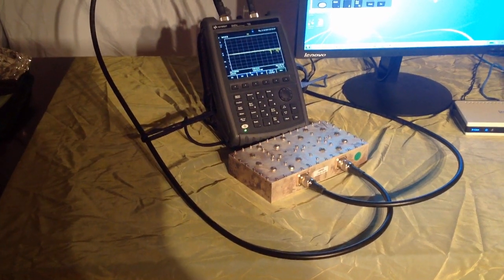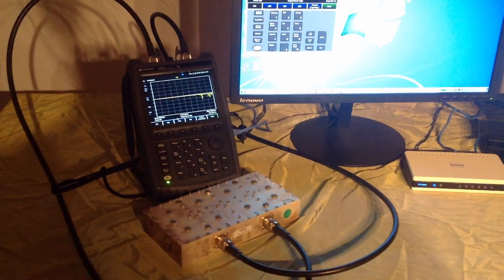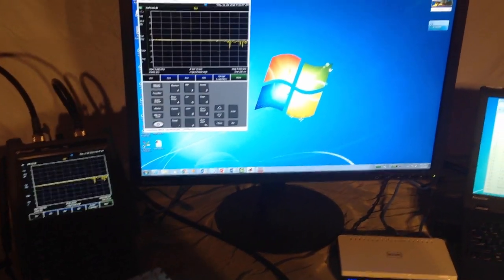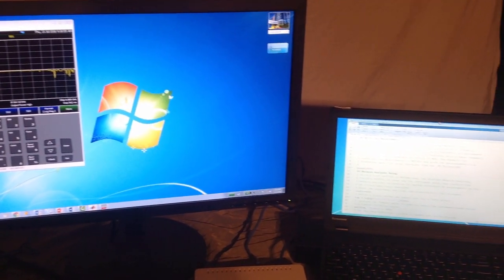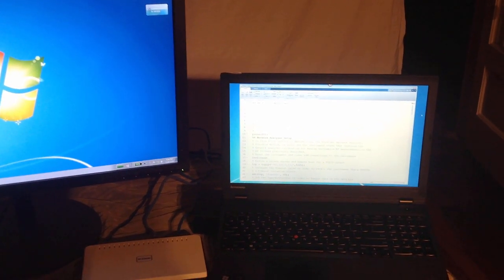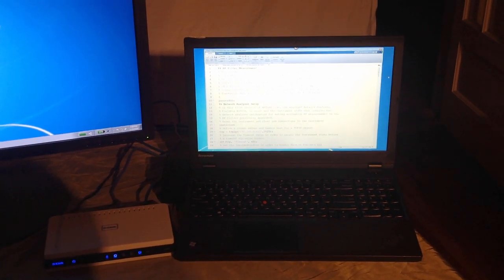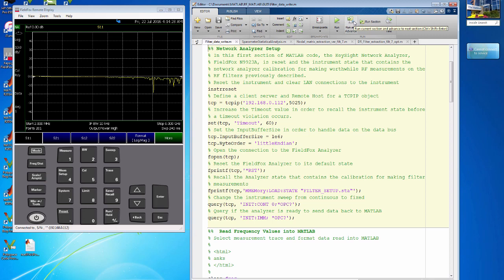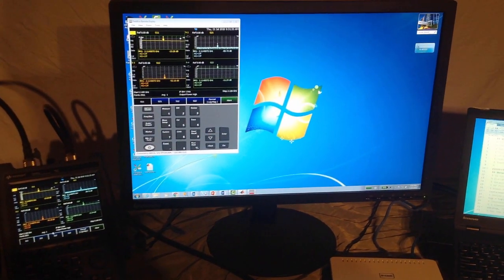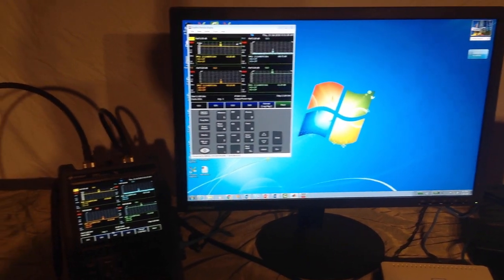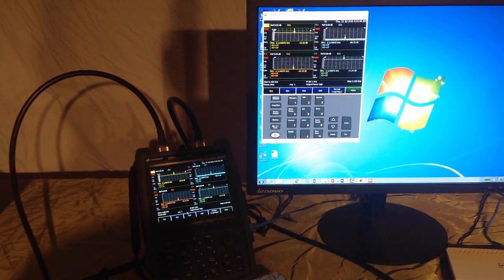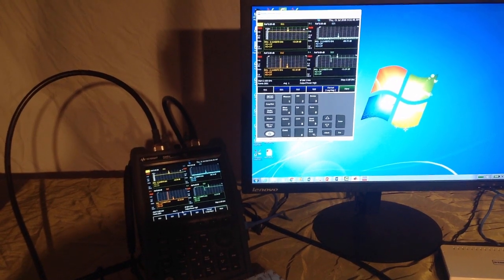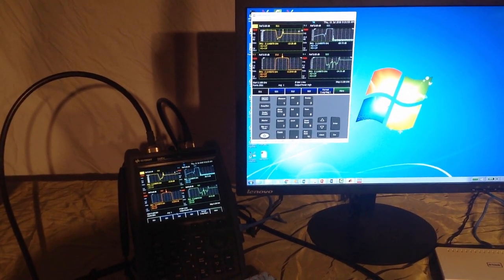Here you can see the measurement setup. The cavity filter is connected to the Keysight FieldFox network analyzer by type N cables, and the analyzer traces are mirrored on the display. To the right of the remote display is the MATLAB script used for interfacing with the network analyzer and extracting measurement data back into MATLAB. We now begin executing the script for the MATLAB Keysight VNA interface. The first thing that occurs is setting up a connection between MATLAB and the instrument and recalling the proper calibration state. The script then reads in frequency values and S-parameters for each of the four traces, putting each trace into a hold condition as data is read in, with sequential traces becoming active.